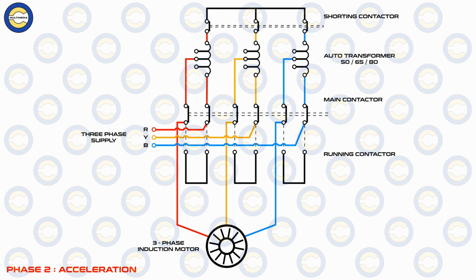Then in step 2, that is the acceleration period, as the motor starts, it proceeds to accelerate with the reduced voltage and hence reduced torque. The torque is proportional to the square of the applied voltage, meaning if the voltage is 65%, the torque will become 0.65 squared, so roughly 42% of the full load torque in the example case that we have taken.